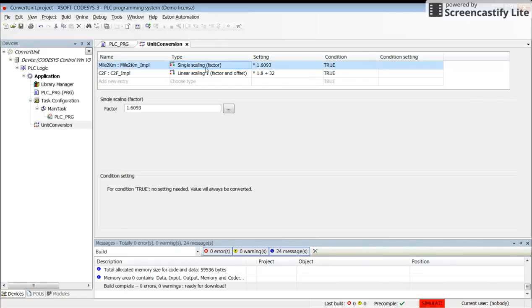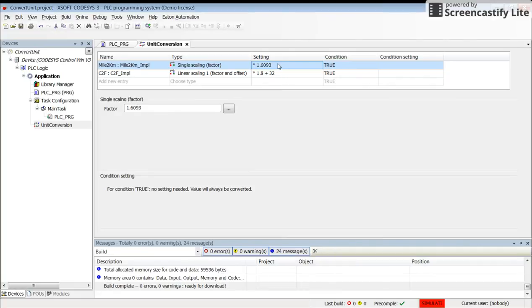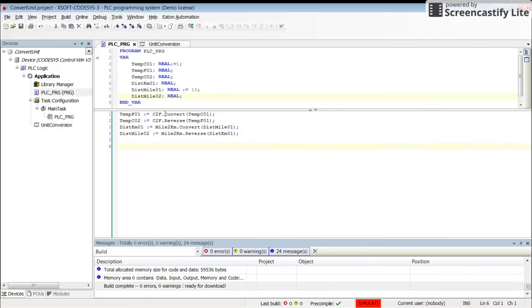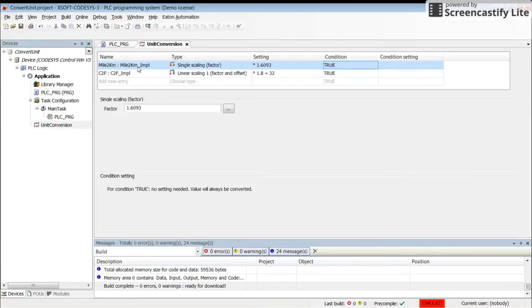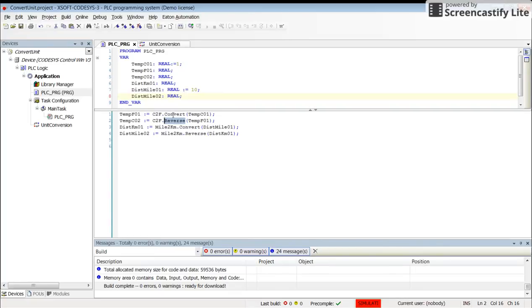For each one, you need to determine the type, whether it's an offset, a factor, factor and offset, and so on. Then you need to determine the parameters in it. If it's only a scaling factor, then you need to determine the factor and condition. In the main program, you need to use the name of the unit conversion. We have C2F and mile to KM, so you use the name, then put the dot, and select either convert for forward conversion or reverse for reverse conversion. You can use it as a function block wherever needed.